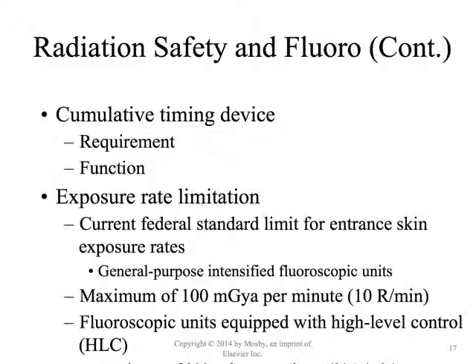In addition to that, we will have some kind of timing device. The timing device is just telling us, hey, 5-minute reminder, you've hit 5 minutes of fluoro time, right? And it's required on all fluoroscopic machines, but it is not actually tied to any kind of reporting. Like it doesn't say anywhere that the patient was exposed to over 5 minutes of fluoroscopic time. We can limit the exposure rate on fluoroscopes, and so there are different settings for that. So if you're trying to do extremity work, use the small exposure rate. It's a fairly easy thing to switch over.